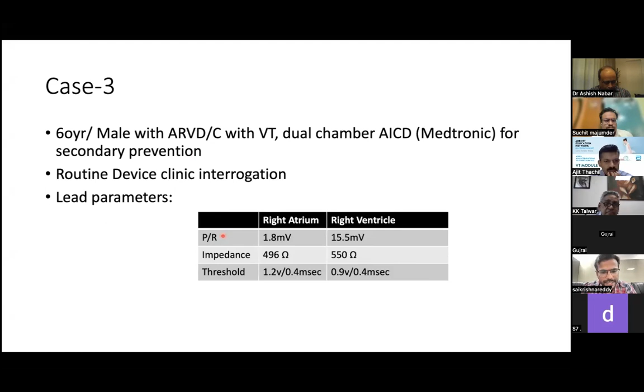And then this is called an interval plot. So the normal parameters like P wave amplitude, R wave amplitude, impedance, threshold, everything was normal. But if you look at the interval plot, what is happening is the device is detecting multiple high rate non-sustained episodes. And if you look carefully into the interval plot, the full thickness circles are ventricular channel signals, and the empty square boxes are atrial channels.